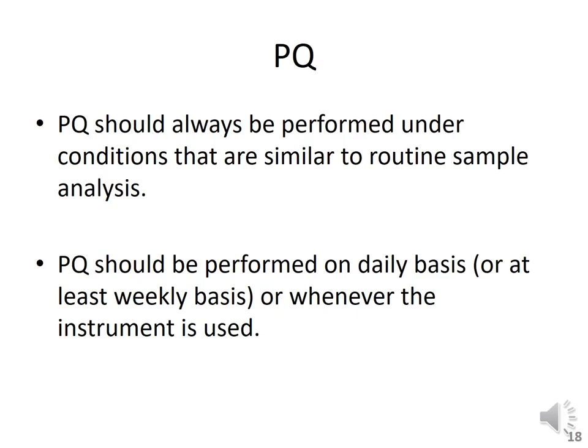If the instrument is not in use on a daily or weekly basis, whenever you are using the instrument, you have to do the performance qualification, and you have to keep the record of the performance qualification, and it will help you in maintaining the instrument for a longer time. Okay.